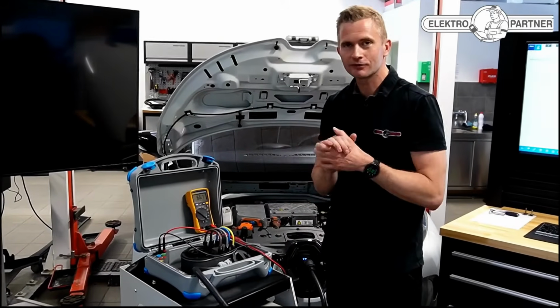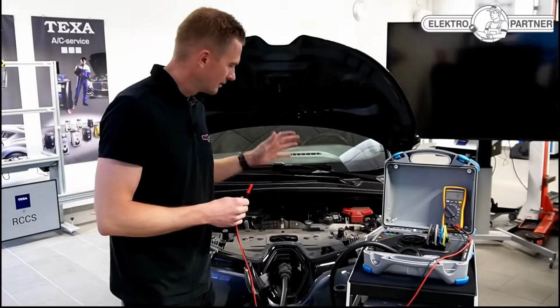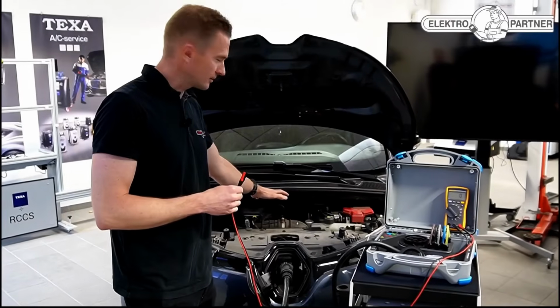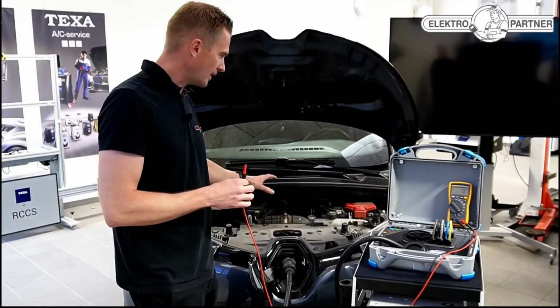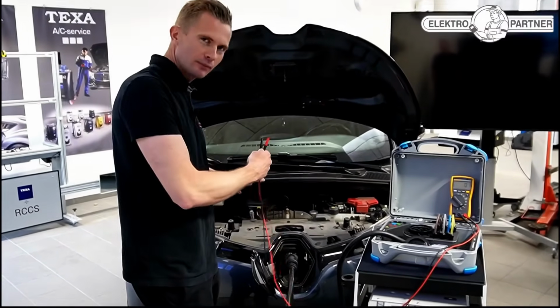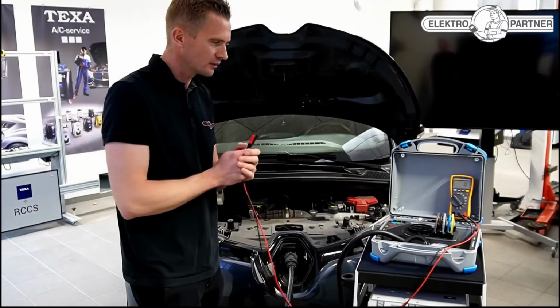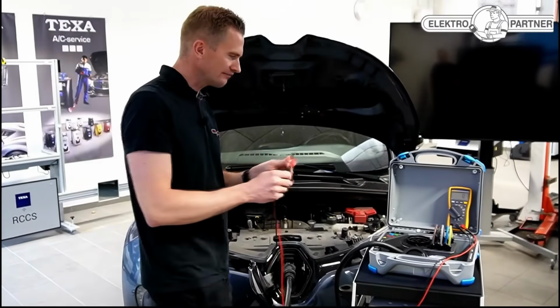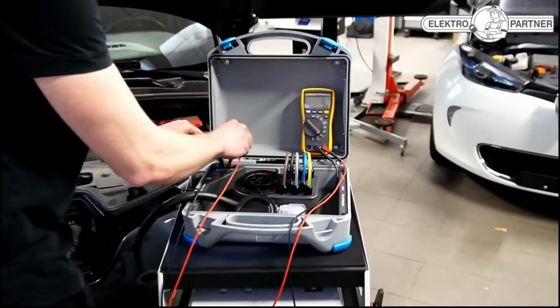Let's try measuring one that's fault-free and see if that gives us any more insight. I'll try to do the same measurement on this Renault Zoe. This is the one without any faults. Granted, it's a slightly different model, but I still expect these capacitors to be pretty much the same. So let's try measuring between the phases on this one.